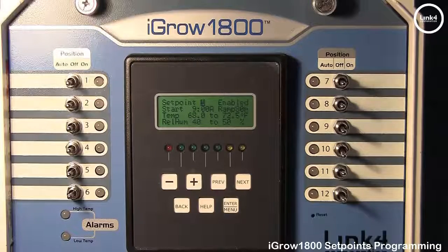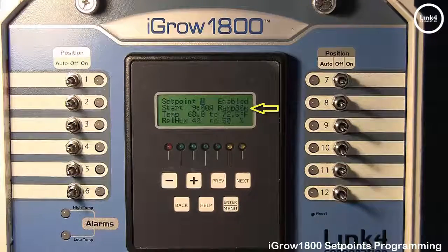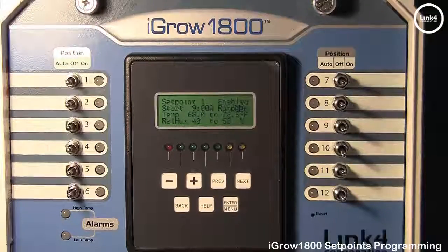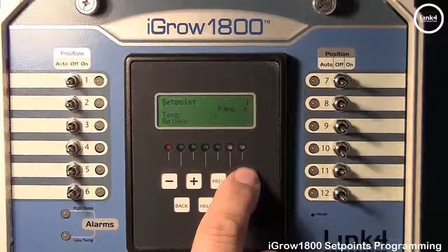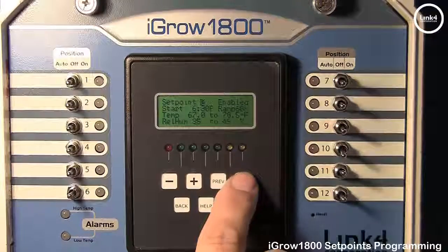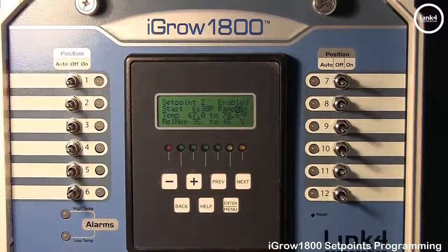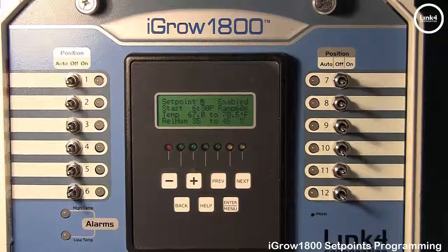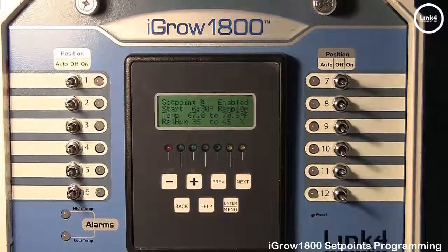In addition, you have the option of a temperature ramp between each set point. Ramping allows you to make smooth transitions within the greenhouse so that plants don't experience temperature shock. And what we'll do is set this ramp for set point 1 to be 30 minutes. And we'll go to set point 2, and we'll make this ramp be 60 minutes. Of course, ramp times can also be set at 0, and in this case, there would be an immediate step transition of the set points themselves.